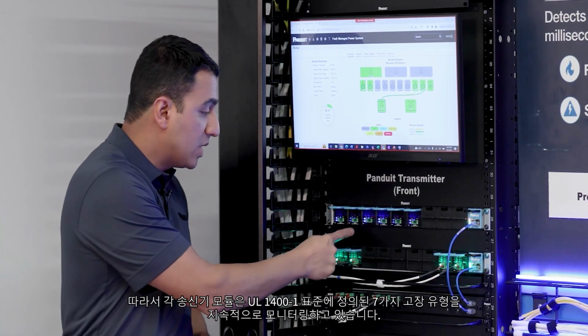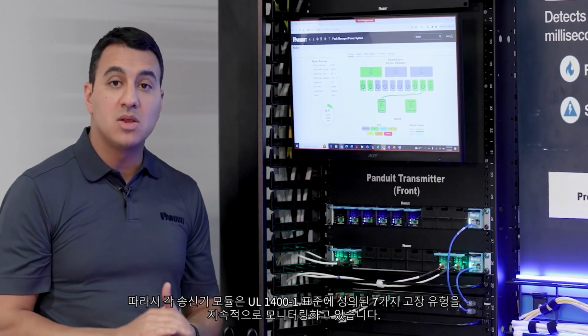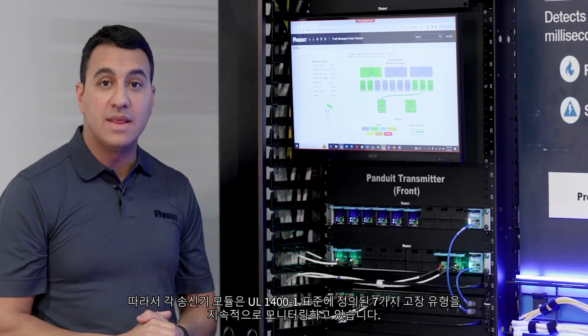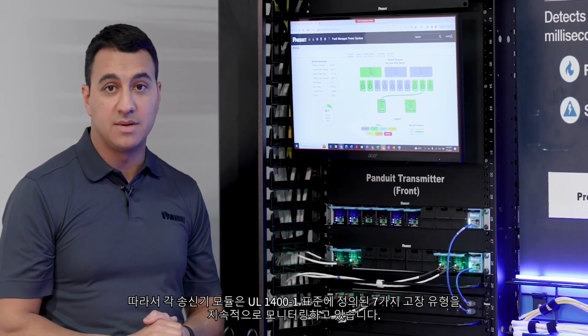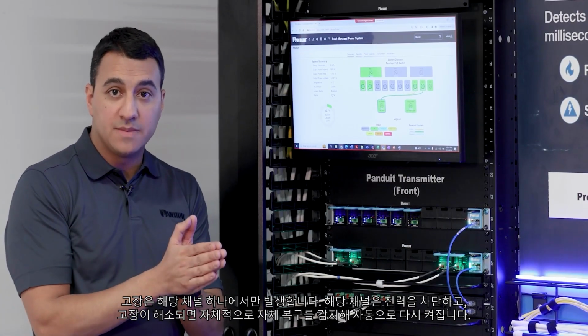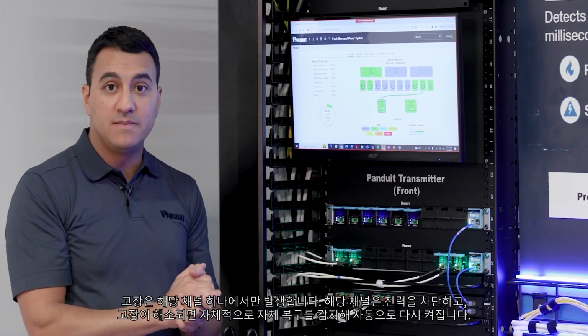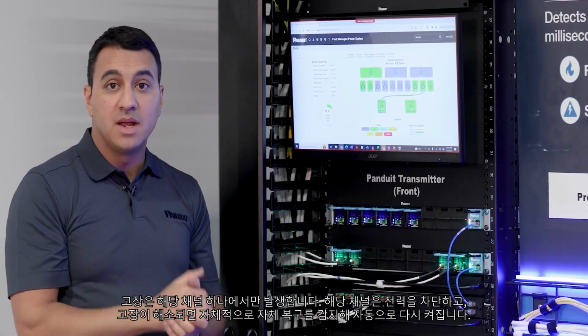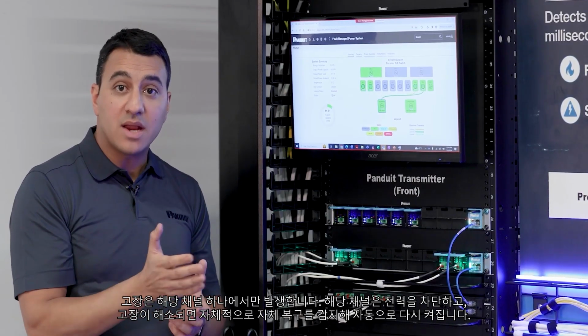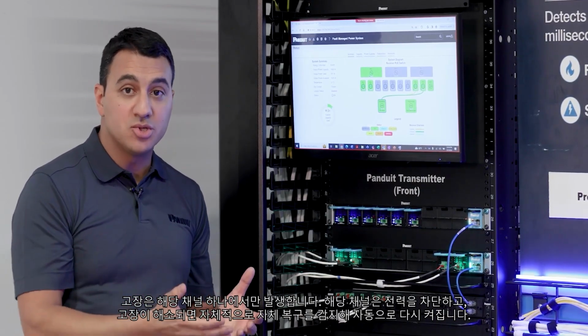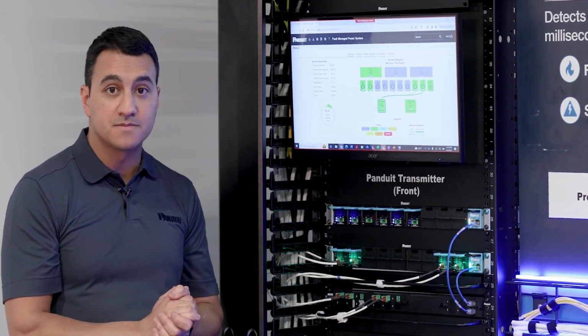So each one of these transmitter modules is constantly looking for the 7 faults that are in the UL 1400-1 standard. Once a fault occurs, it only occurs in that one channel. That channel turns off. If the fault clears, that channel recognizes that. It's self-healing, so it will just turn itself back on.